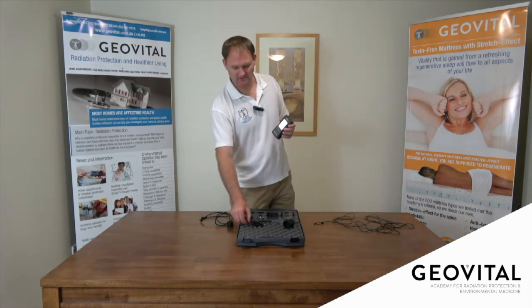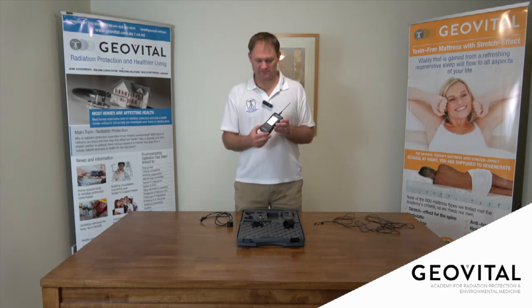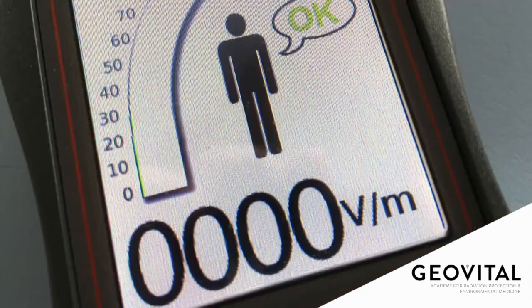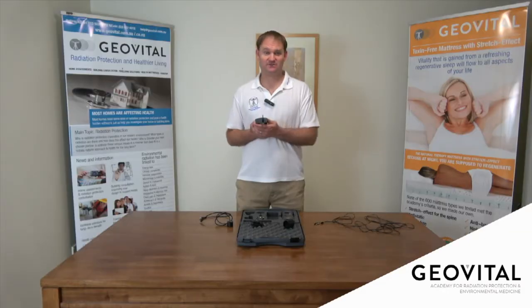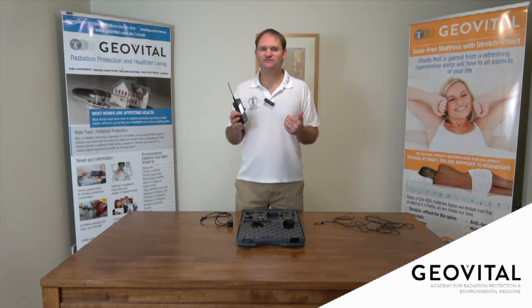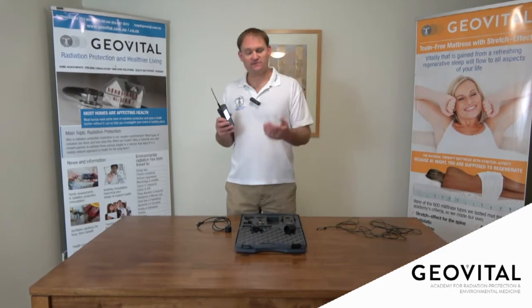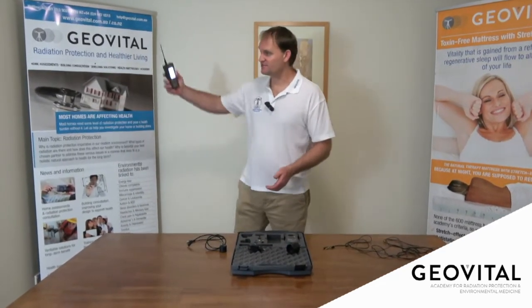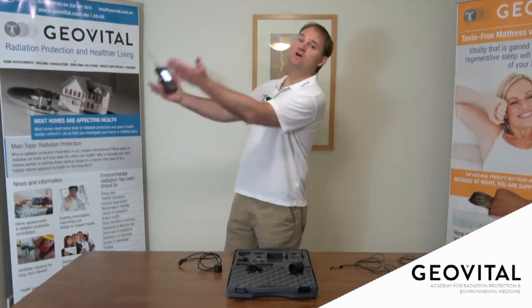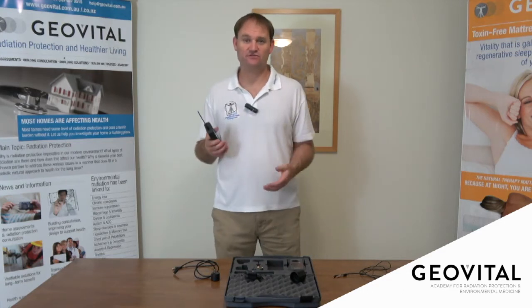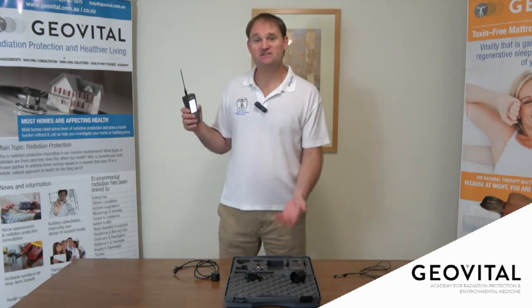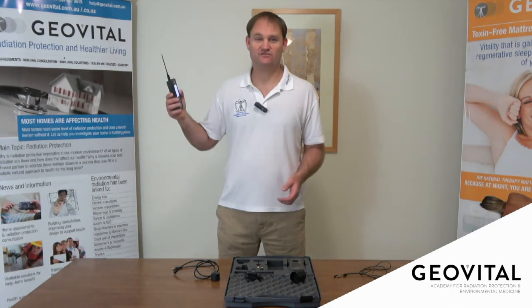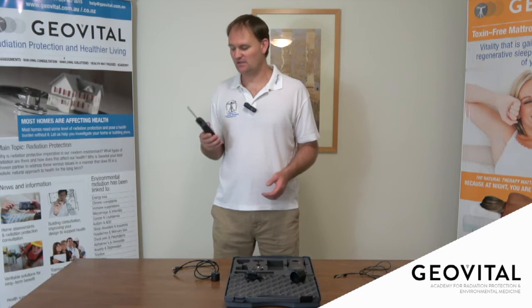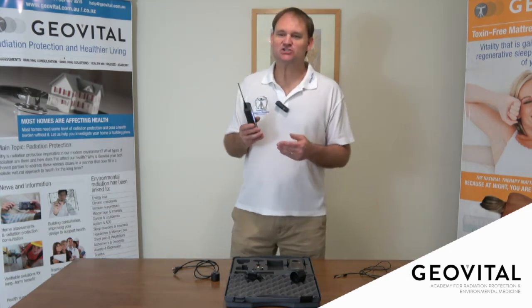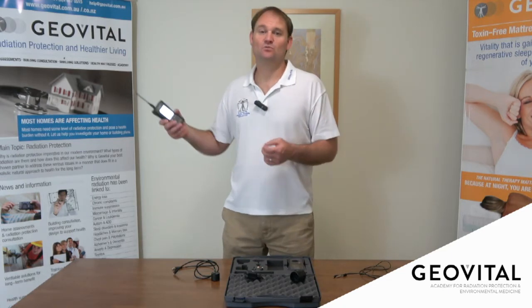Electric field assessing is more the claim to fame for this instrument, so make sure you put it back to volts per meter. Now it's very important to realize that this instrument measures a difference between surfaces. For example, if I'm standing on a floor and measuring a wall, let's say I'm getting 400 from the wall and 300 from the floor, this instrument is going to show me the difference, so it will show me 100. If there was nothing on the floor and I measure the wall that's got 400 on it, it would show me 400.